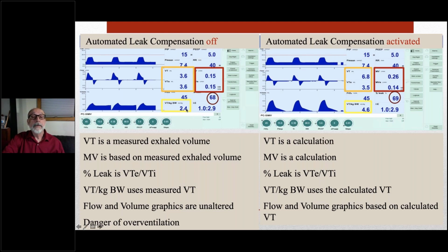And so the per kilo tidal volume in this example is 2.4 ml. You can see the large leak. The tidal volume does not return to 0. You can see the leak here in the flow waveform. So the tidal volume that the ventilator displays and uses for regulation of inflation pressure is the exhale tidal volume.